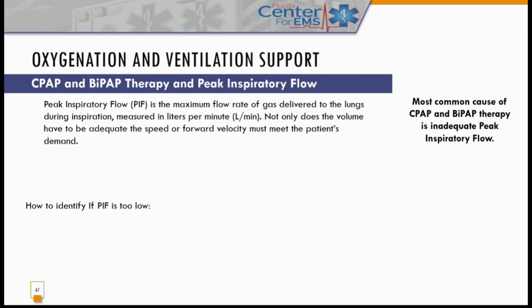If they inhale and the needle goes to 0, the peak inspiratory flow is not fast enough. A person in respiratory distress, the velocity has to be probably right around 65 liters a minute. And a lot of these devices will give you 5 of CPAP on 8 liters. How do I get from 8 liters to 65? A lot of them use it as a venturi. All y'all know about venturis, that if you narrow the flow, it speeds up.